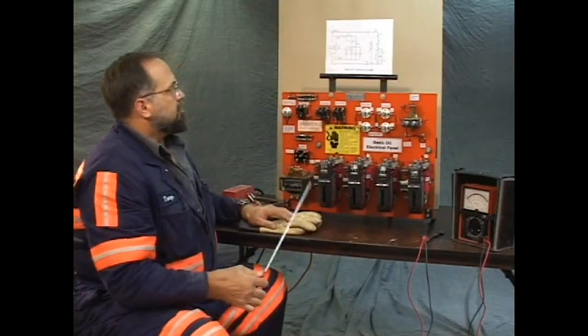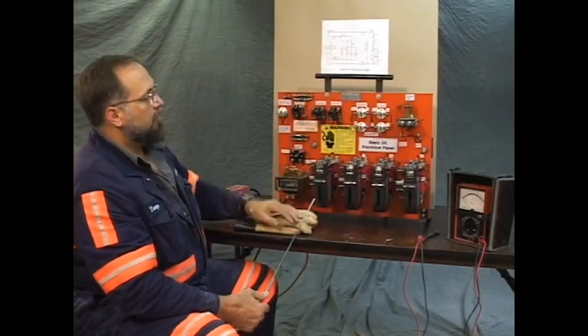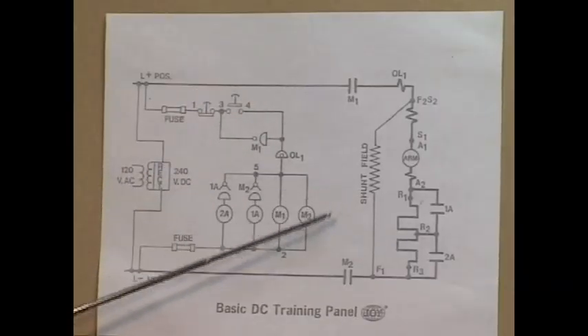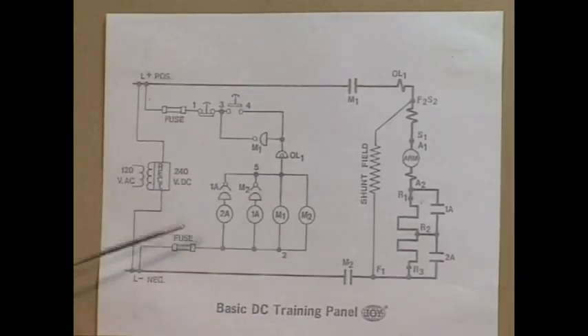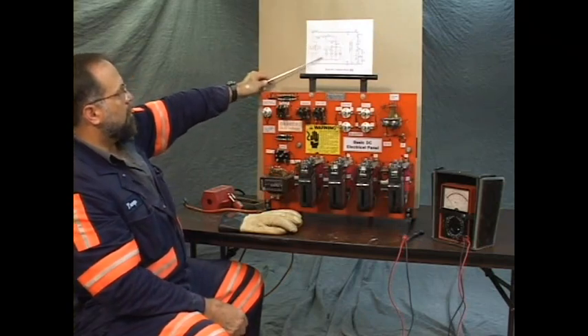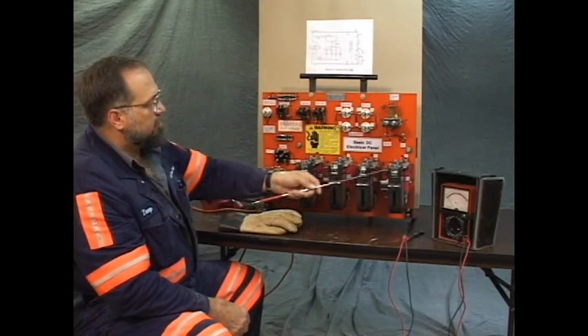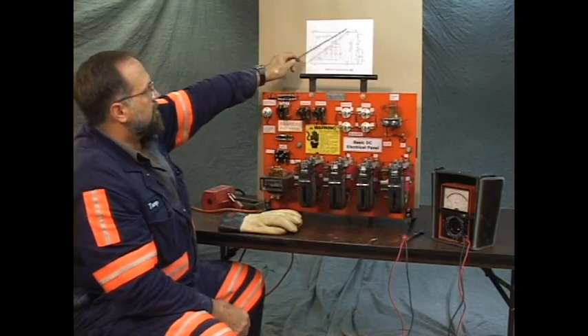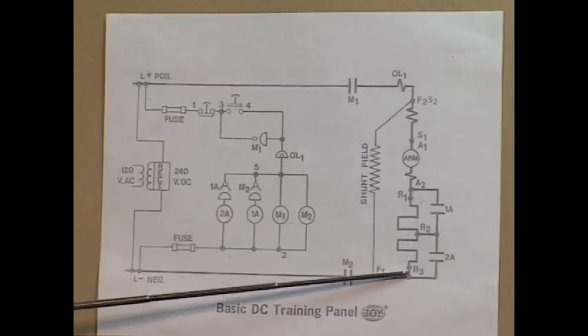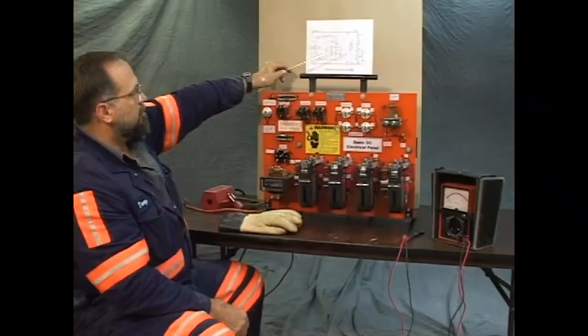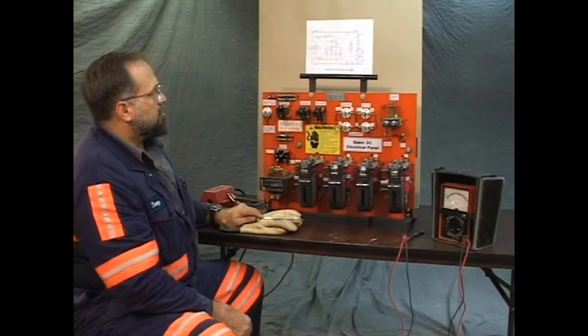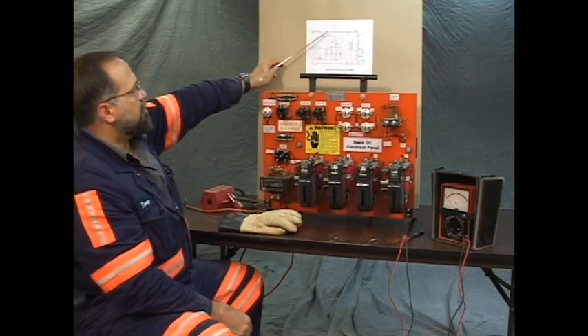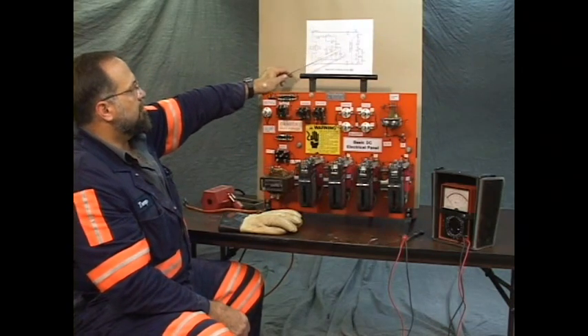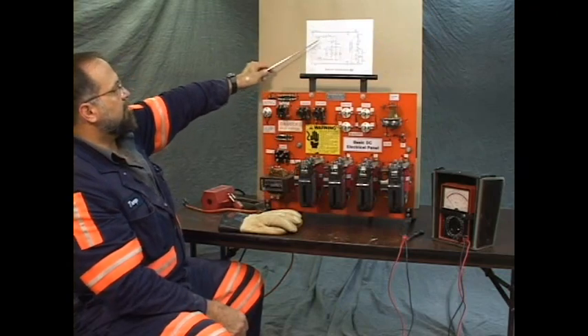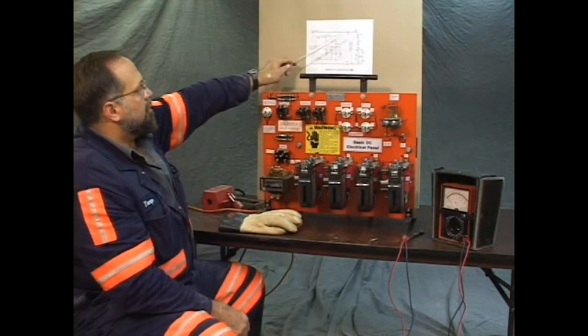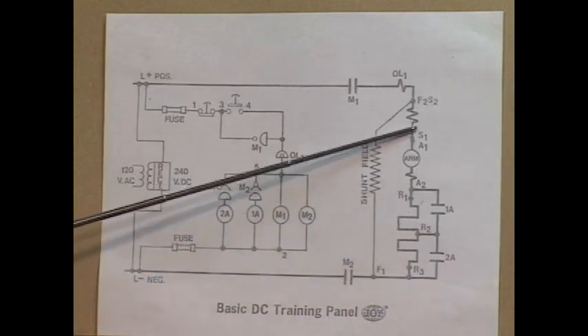Before we apply our instrument though, let's talk. Now, this part of the circuit here is the control circuit. These, the switches and the coils, bring about an action to close the contactors. And when the contactors close, they put the power to the motor, through the starting resistors and to the motor. That's where our problem lies. The control is all operating as it should. This part is doing well. There's no use to spend a lot of time checking the control when it's operating correctly. But this part of the circuit is not functioning correctly.